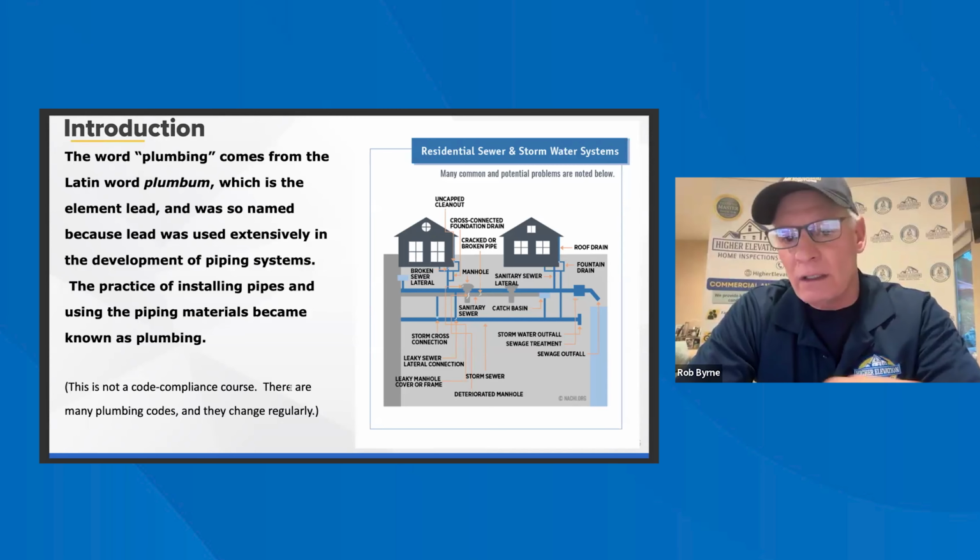When you're inspecting tankless systems, again, we just spoke about it, you want to check to have proper venting. The water temperature, we talked about that earlier. You want to make sure that it's not too hot. And at the same time, you've got to make sure you have hot water, because that's our job when we go there, to make sure that you have hot water, because it's a necessity. So those are things that you would check for on a regular water heater, even though it's tankless: the functionality of it for the hot water and the scalding aspect of it.